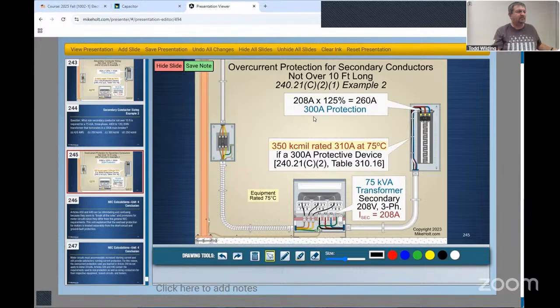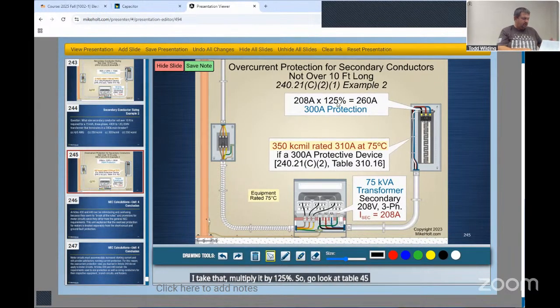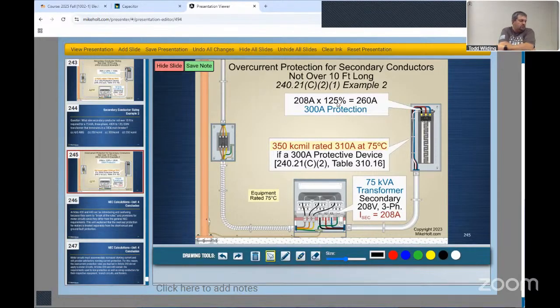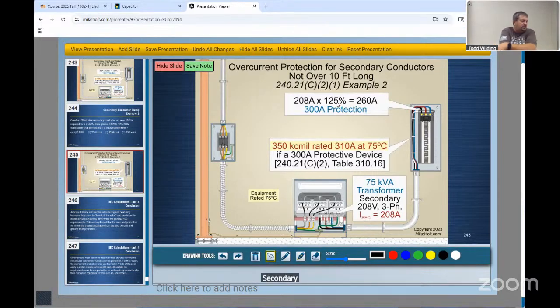I take that, multiply it by 125%. So go look at table 450.3(B). Secondary protection. Why am I not using the 167% on secondary protection instead of the 125?